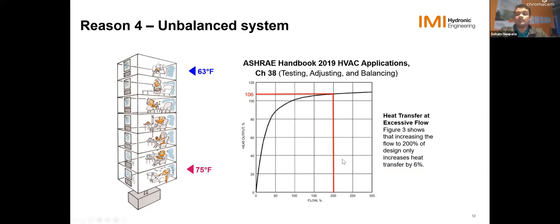So this chart here is from ASHRAE Handbook from 2019. So what it shows is the characteristics of a typical heat exchanging device, heat exchanger. So the way it works, as you can see, it's not a linear curve, is you increase your flow to 200%. So 200, double the design flow. What you see is only 6% increase in heat transfer. You see the big difference from 100% flow to 200.